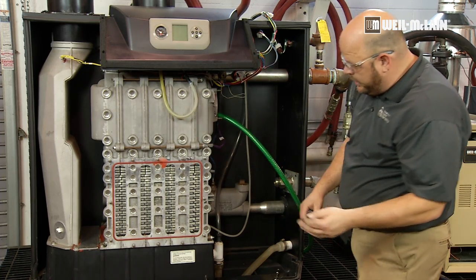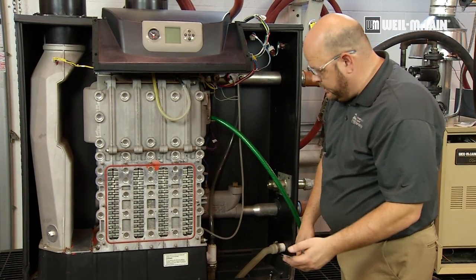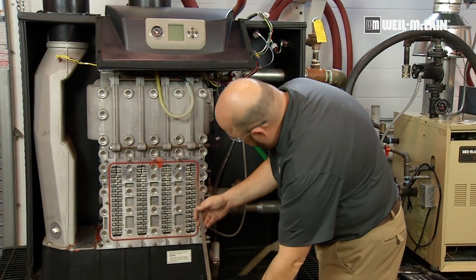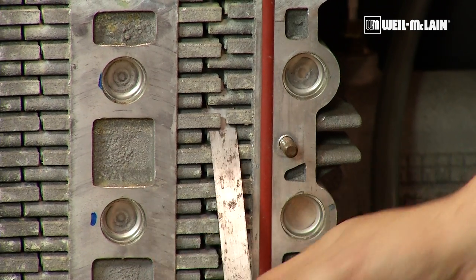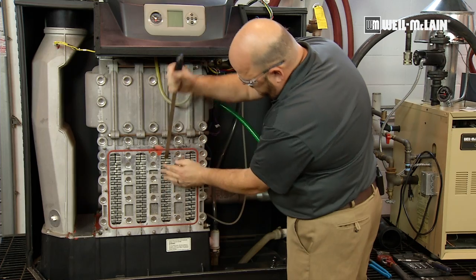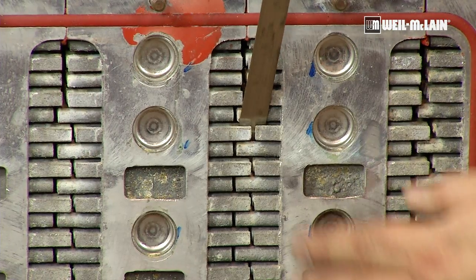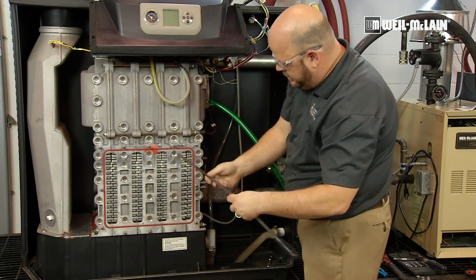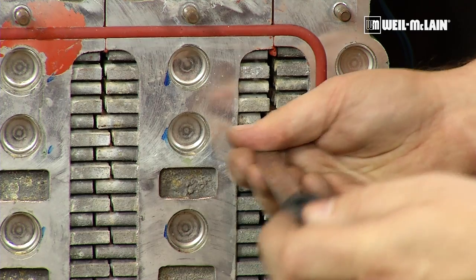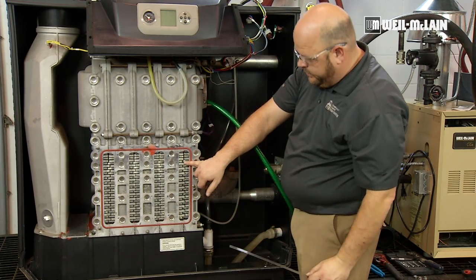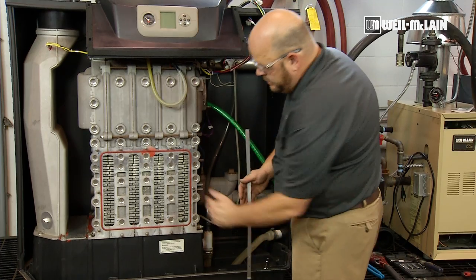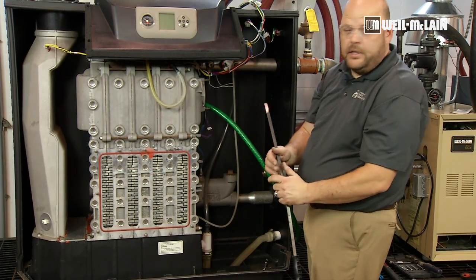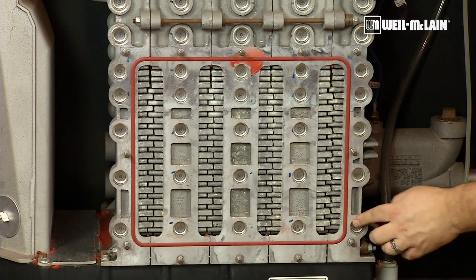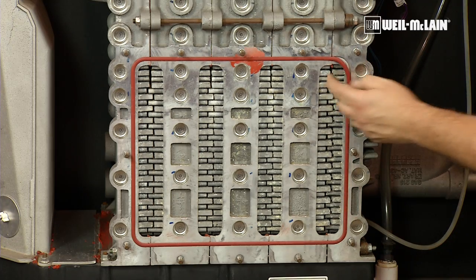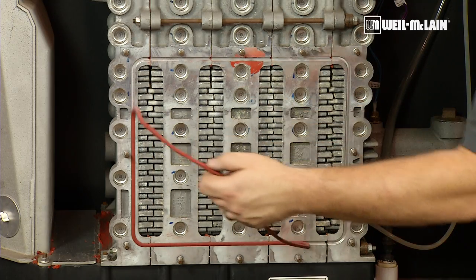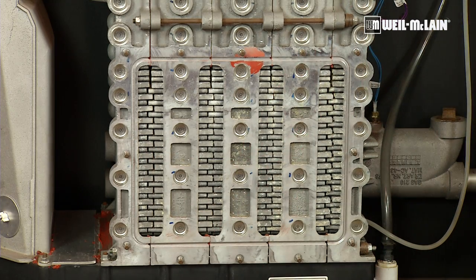There are three directions we're going to want to clean the heat exchanger pins. Start off, we can clean between all the pins up at a 45-degree angle, down at a 45-degree angle, and we can go straight in. We will go up, down, and in through every set of pins on every flueway through the heat exchanger. And we have our cover plate gasket material, which you can roll out with your finger and then pull out of the boiler.